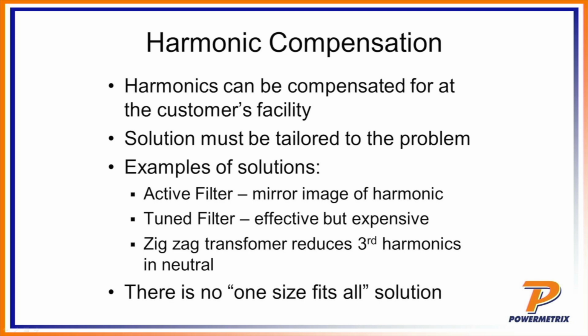Once again, those are very expensive because a lot of times this is done digitally. So it may depend on the level of harmonics and the frequency of the harmonics. Another way of doing that is a tuned filter, which is a filter that is basically designed for a particular pass band. A lot of times it's going to be a low pass filter, meaning that it's going to pass the 60 hertz, but we're trying to get rid of all those higher level harmonics. Once again, very effective, but can be very expensive. If it's a passive filter in particular, it's apt to generate a lot of heat, and so you're going to have some very large devices, very, very expensive, a lot of heat being generated, some of the issues that can come up with that.